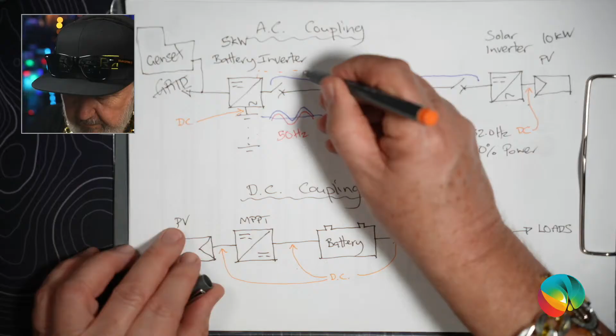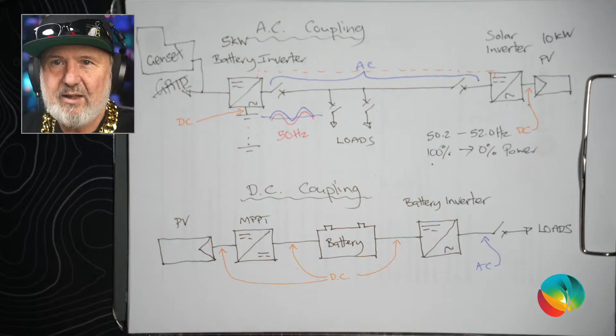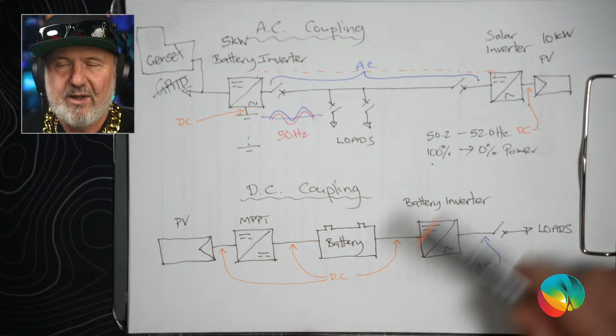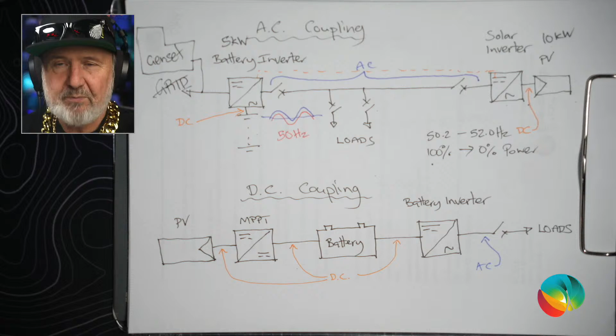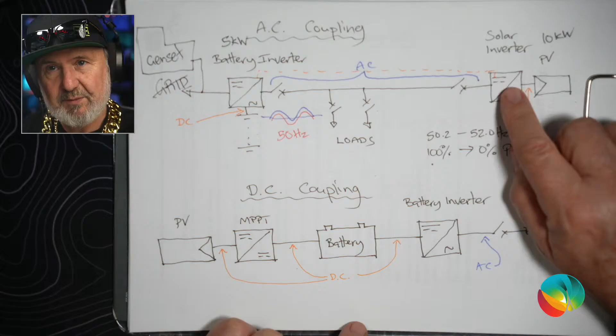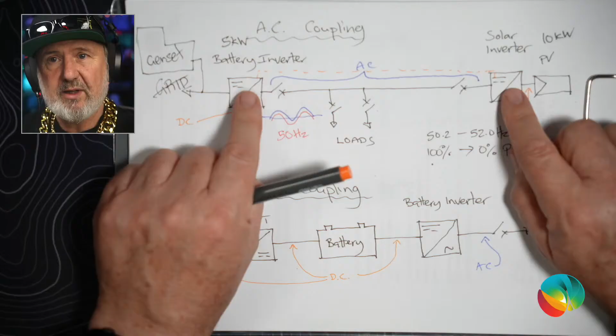And so that data cable that goes between the battery inverter and the solar inverter is actually controlling in data speed the output power of this solar inverter. So RS485 runs at many kilohertz, 10, 15, 100 kilohertz. So it can operate very fast. But it does now mean that this solar inverter must be compatible with the battery inverter's comms. And now we've got a much narrower range of options in terms of product.